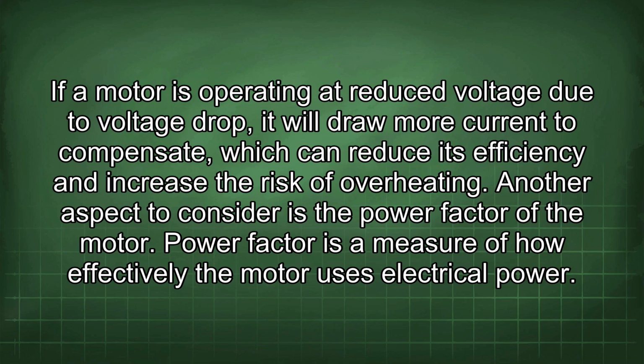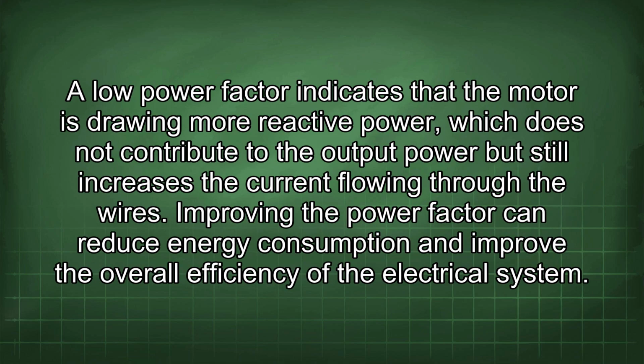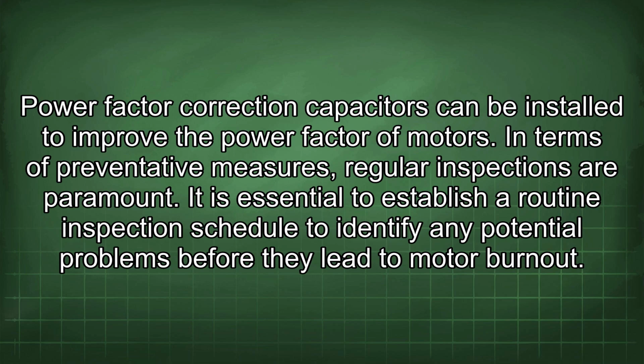Power factor is a measure of how effectively the motor uses electrical power. A low power factor indicates that the motor is drawing more reactive power, which does not contribute to the output power but still increases the current flowing through the wires. Improving the power factor can reduce energy consumption and improve the overall efficiency of the electrical system. Power factor correction capacitors can be installed to improve the power factor of motors.